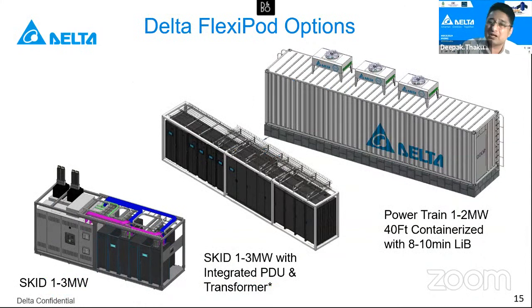Some examples of our FlexiPod, which we created along with customers, are SKID architecture of 1 to 3 megawatts. It's an integrated panel along with the UPS panels, input, output, along with the batteries, as well as the UPS, in a skid form prefabricated at the factory and just installed at the site. Similarly, a skid of 1 to 3 megawatts with integrated PDU and transformers. So much space is occupied by PDUs. If you consolidate the transformer at one location and have the PDUs integrated, you can have a skid which can cater to the load and reduce a lot of space.